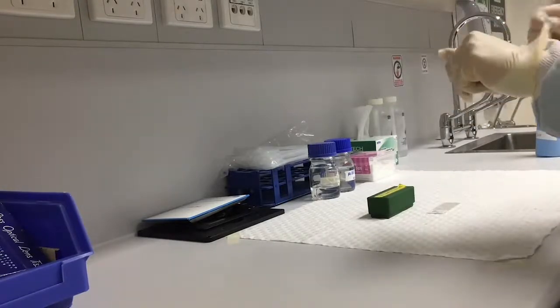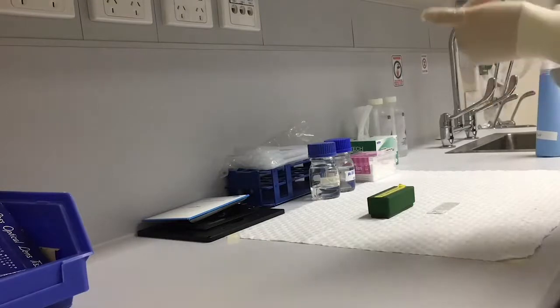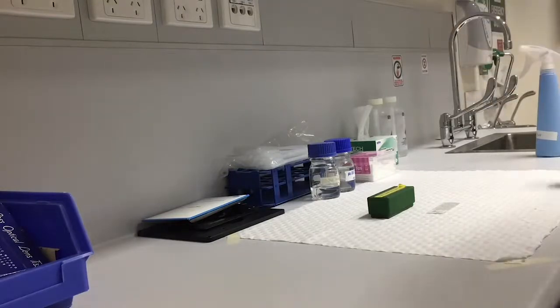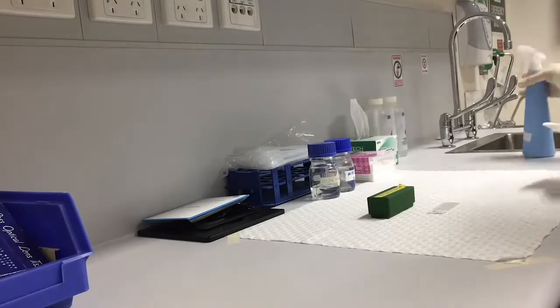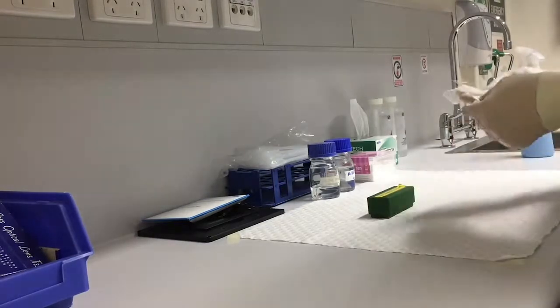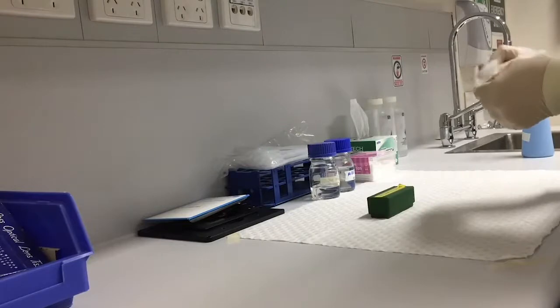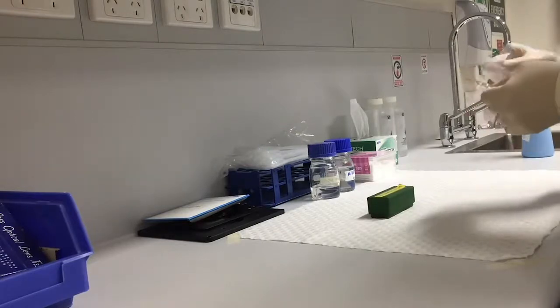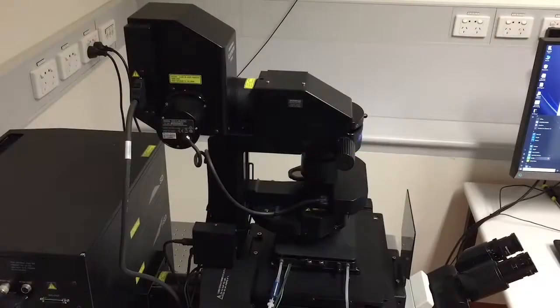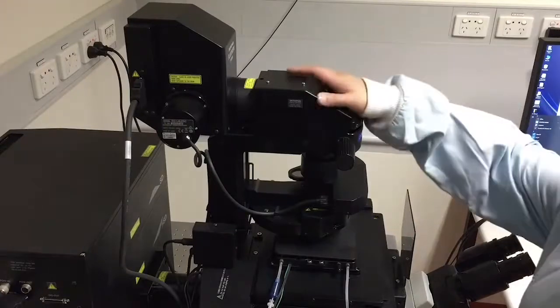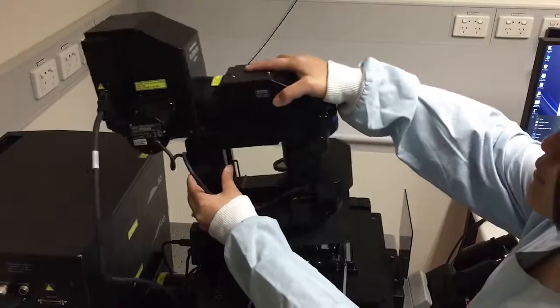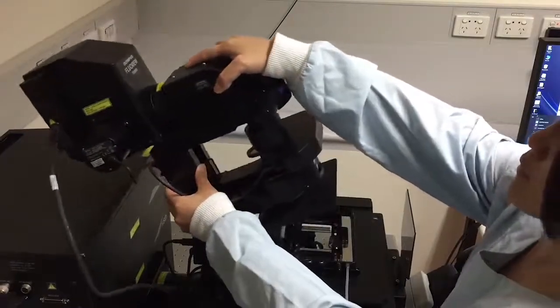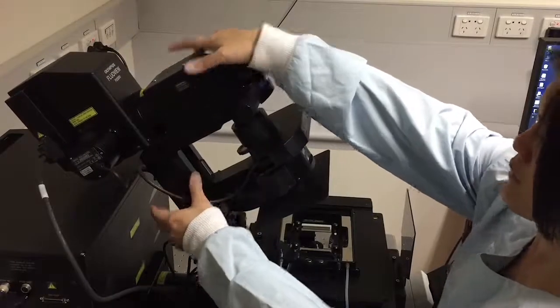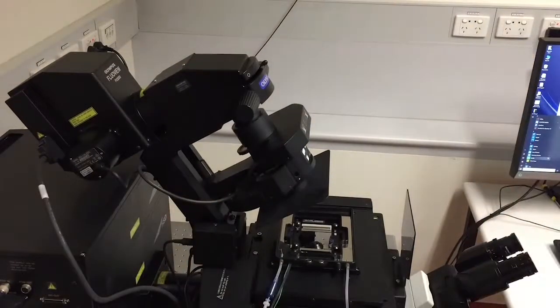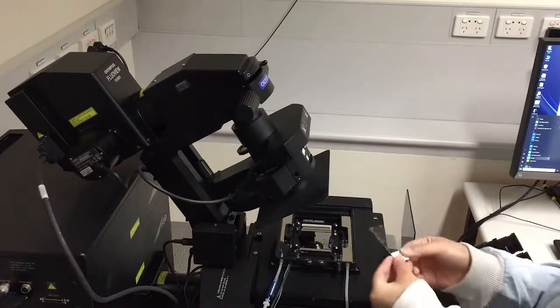Put on a pair of gloves and carefully clean your sample with a Kim wipe and 80% ethanol. Carefully tilt the upper part of the microscope backwards to access the stage. Make sure you support it with both hands. Do not let it fall freely on its own weight.